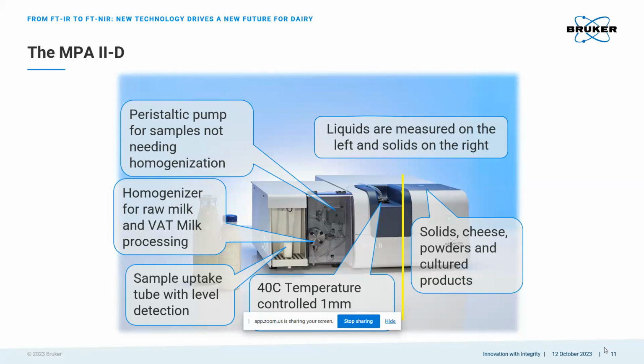Now, the LSM provides excellent precision by analyzing raw milk sample volume that is more than 20 times larger than can be done by FT-NIR analyzers. You can see our 1 millimeter flow cell here, which allows viscous samples like concentrates to be easily pumped. And we also have full software control with configurable sampling volumes and automated cleaning cycles, as well as visible tubing for really easy inspection. So you can see how this is the optimal solution for raw milk due to the semi-automated sampling and the sample transport during which the raw milk is preheated and homogenized before measurement to ensure we get that high precision and repeatability, and again, followed by the automatic cleaning of the system.